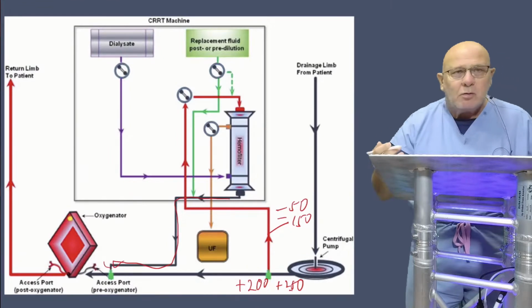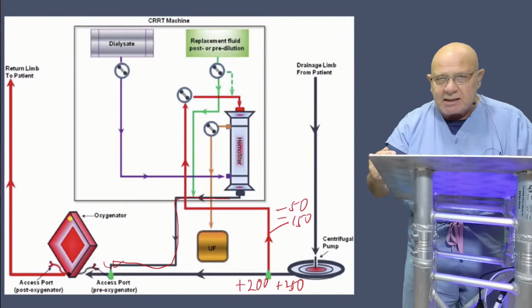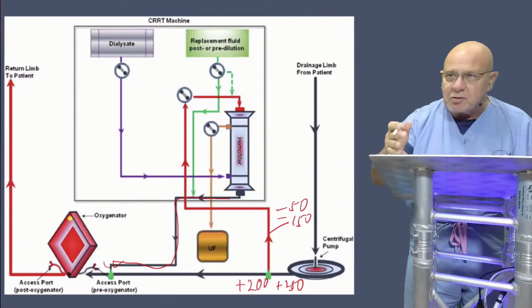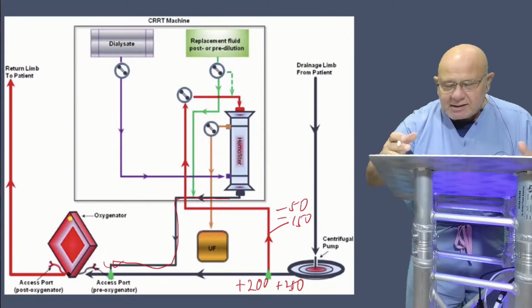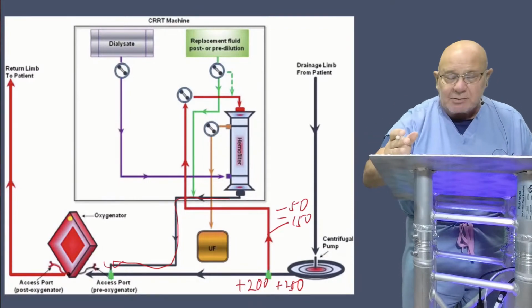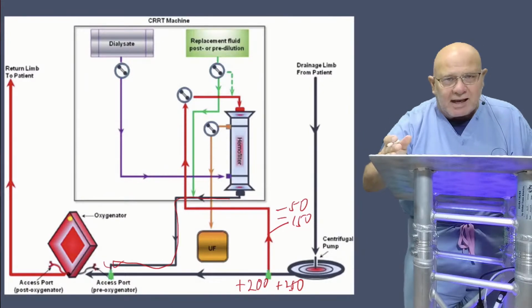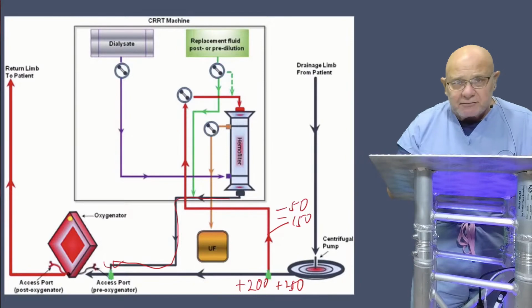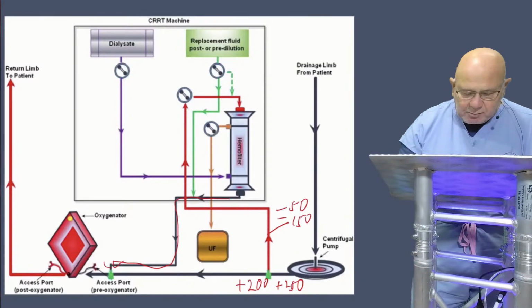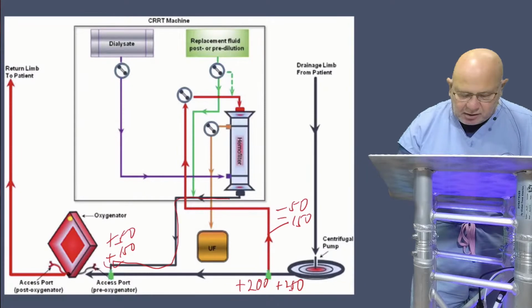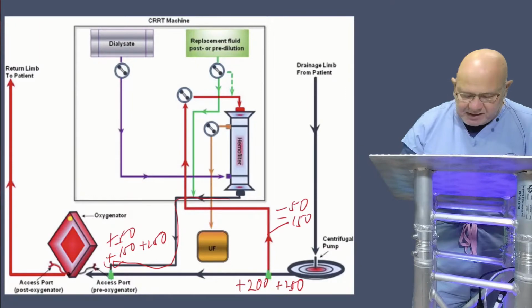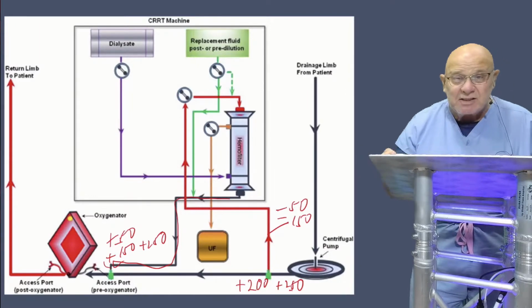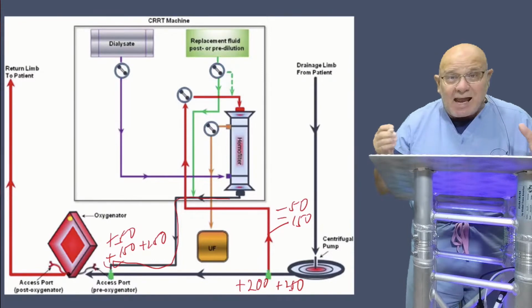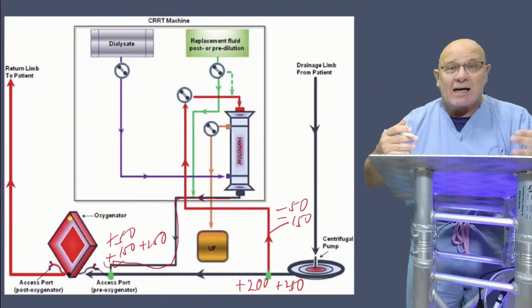Well, there is no CRRT machine that is designed, you're going through a Mahurkar catheter or a Quinton catheter, or temporary dialysis catheter. I need to just say temporary dialysis catheter, be easier. You're going through that, and your normal pressure on this return, if you remember we talked about, is going to be somewhere between positive 50 and positive 150. Maybe it can go up to positive 250 if you're really pushing it. But if you're already at a positive 250 in this line when it's expecting it to be just the resistance through a temporary dialysis catheter, now your return is seeing a very hostile environment.